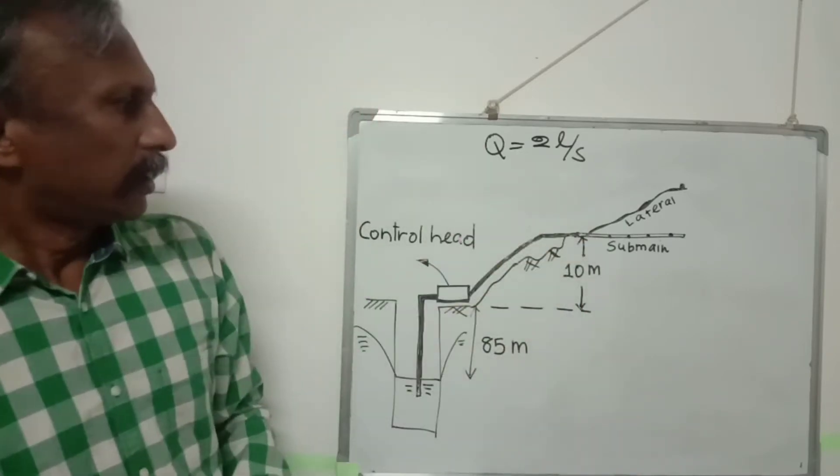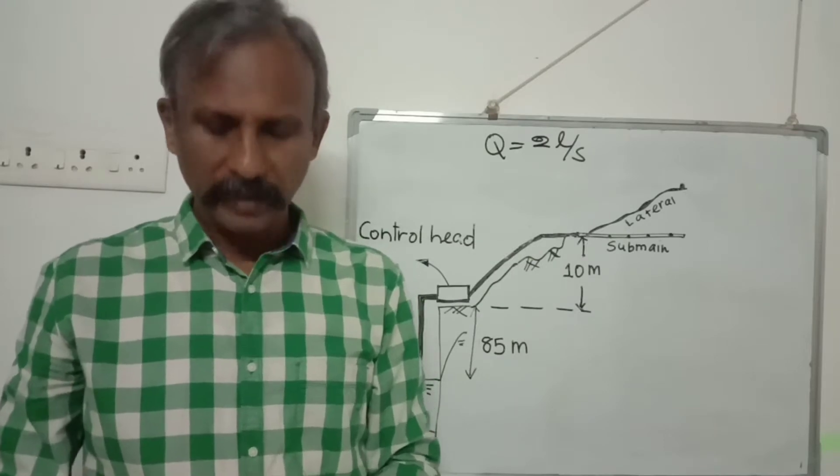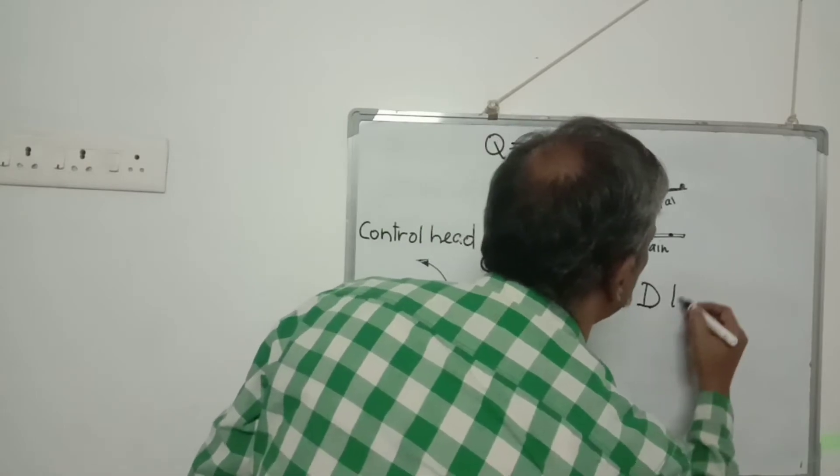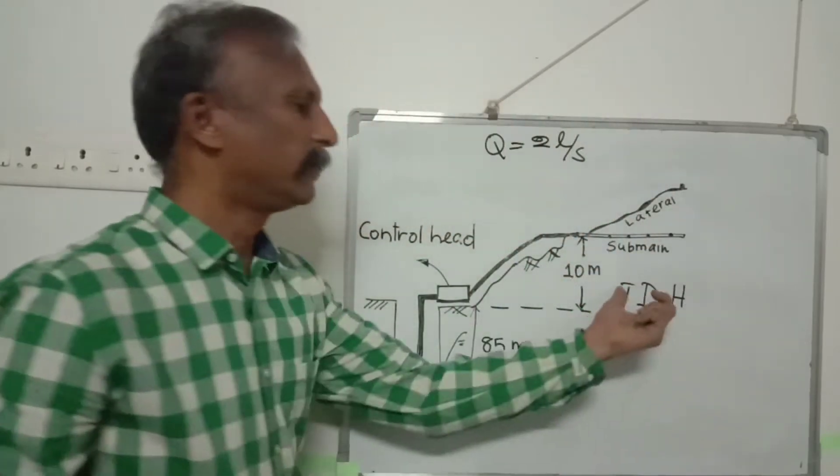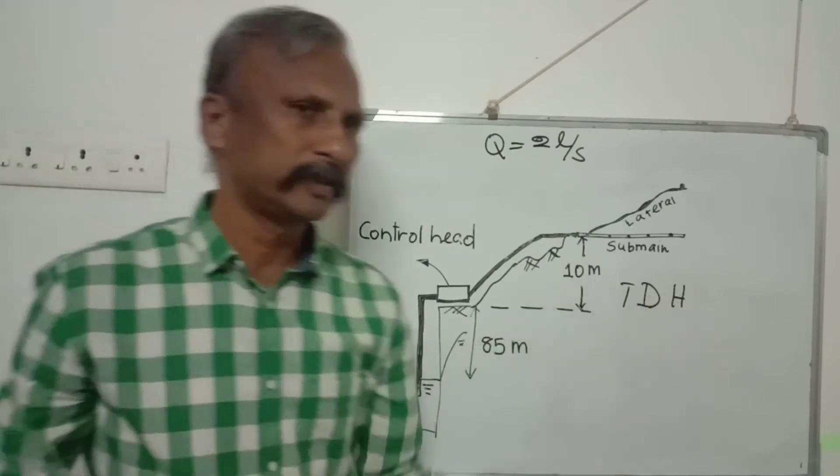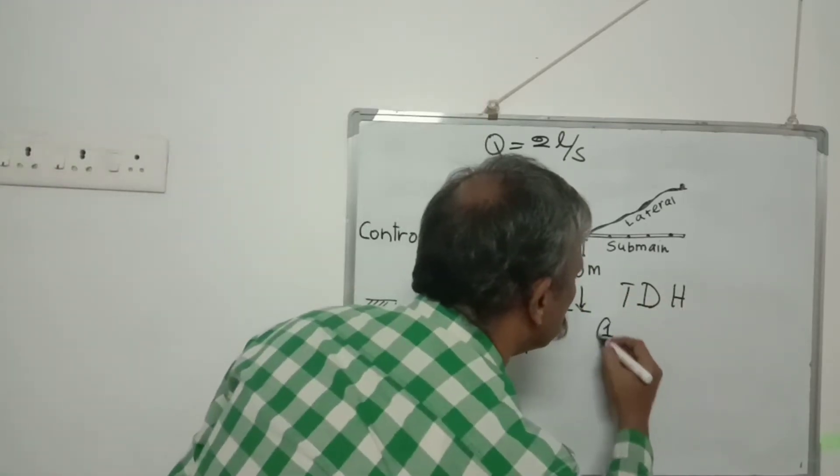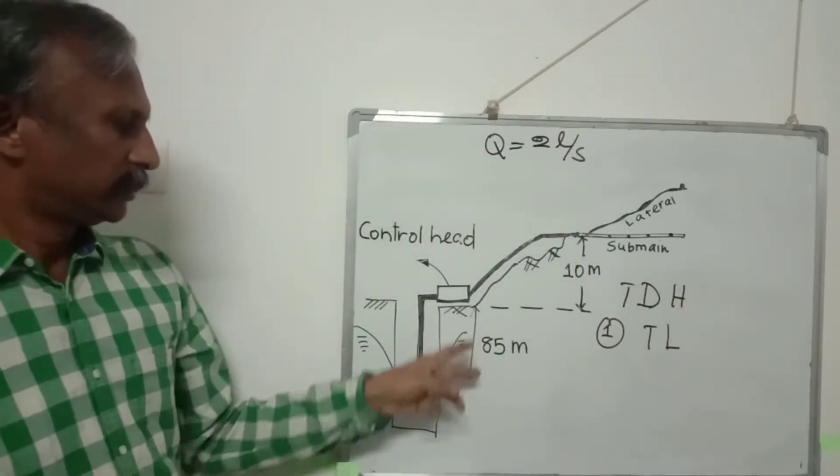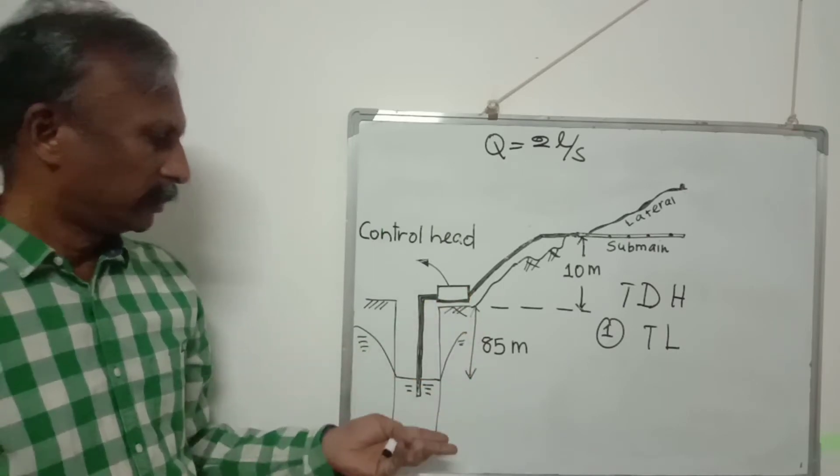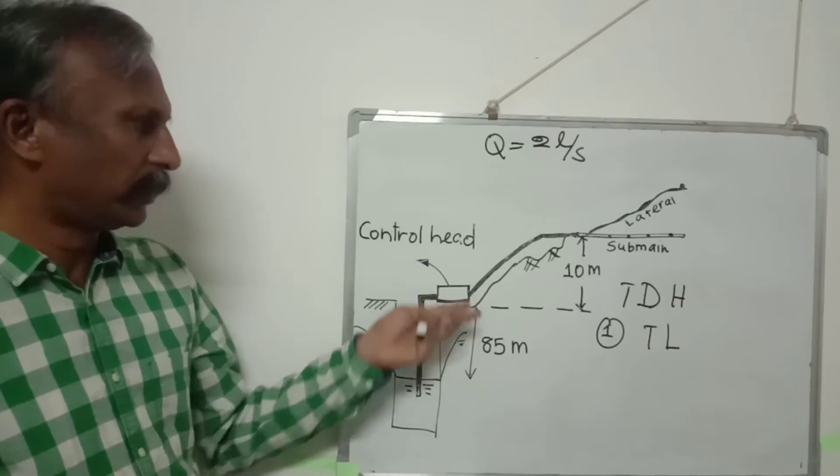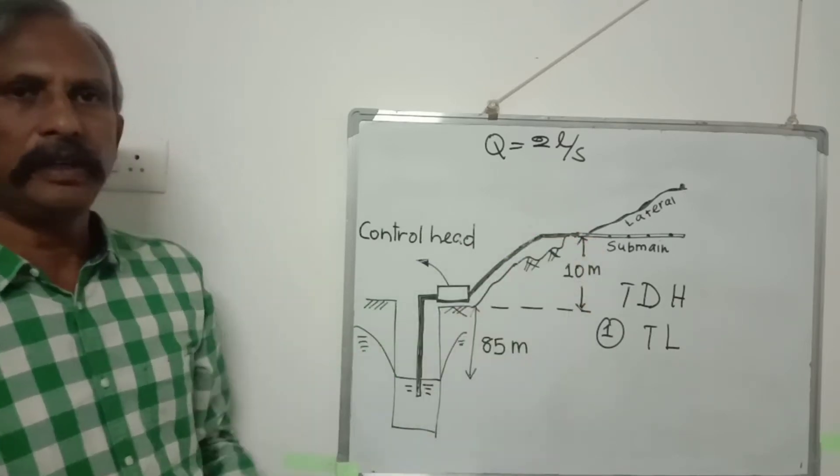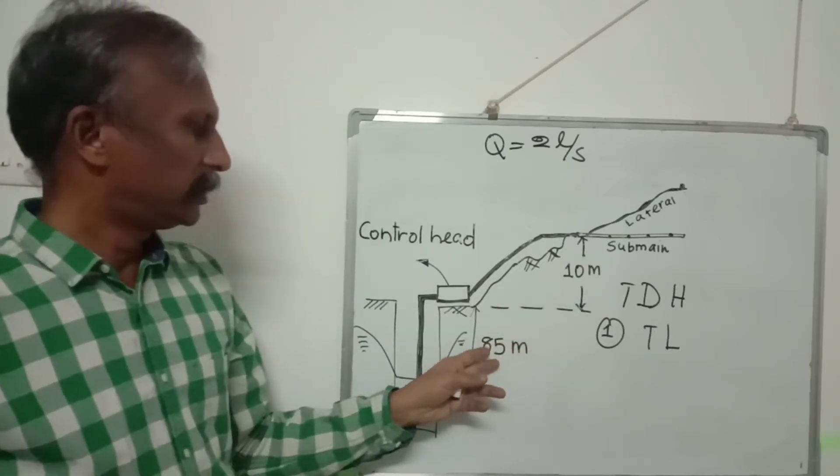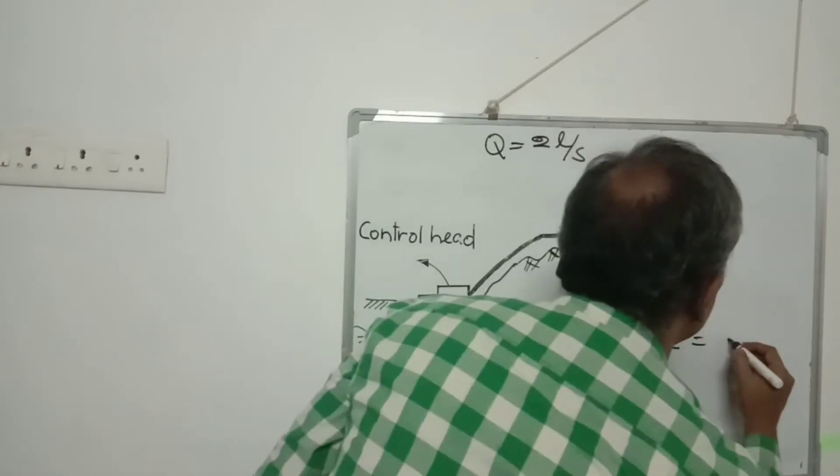After doing these things, we should find out the total dynamic head needed to be developed by the pump. It has a few components. One is total lift. Total lift is this 85 meters - the water has to be lifted from here to the ground - and also the height of the most critical submain from the field level. So this is 85 plus 10 is 95 meters.